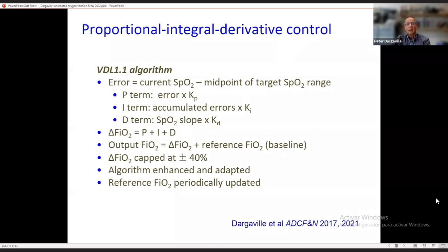And from that, calculating a delta FiO2, a change in FiO2 to be made from the sum of those three terms. And the output FiO2 is the delta FiO2 added on to a reference value, a reference FiO2, which is a reflection of the current baseline oxygen requirement. So essentially all that's doing is asking the question, what change should we now make, knowing what the current reference FiO2 is, what the current baseline oxygen requirement is, what should be the next change in FiO2 in this current iteration of the loop. And for VDL 1.1, the delta FiO2 is capped at plus or minus 40%, which does allow plenty of leeway in the function of the algorithm in turning the oxygen up and down. And the algorithm is enhanced and adapted for the biological system under control, and the reference FiO2 is periodically updated.